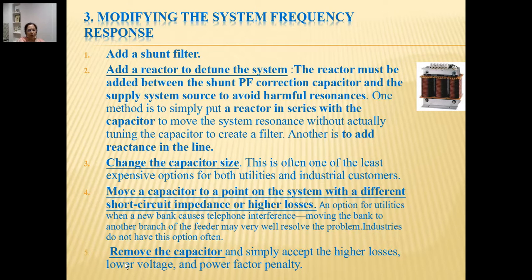And the last option is to remove the capacitor, because capacitors act as sinks for high frequency harmonic currents. Many times these capacitors attract harmonics which are generated elsewhere in the circuit, and it may be causing problems to the loads which are connected where the capacitor is connected, even when the load is not producing harmonics itself. So because of the flow of harmonic currents from the rest of the network towards this capacitor, it may cause problems for the load connected at this end.